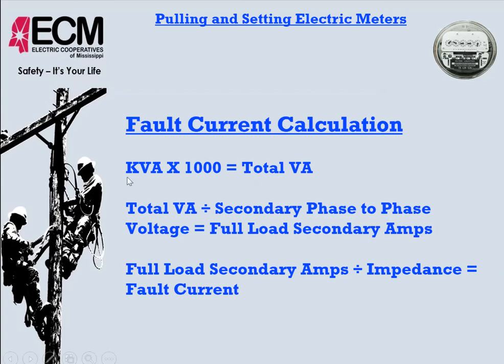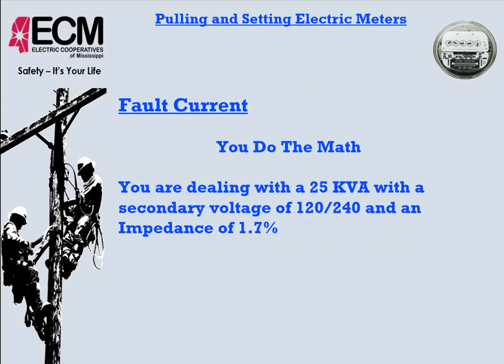So what you would do is take the kVA, multiply it times 1,000, which would give us the total VA, the volt amps, and then take the total volt amps and divide it by the secondary phase-to-phase voltage. So if it was a 120-240 transformer, you would use the 240 voltage, and that would give us the full load secondary amps that transformer can deliver at 100% load capacity. And then we want to divide it by the impedance of the transformer. And I have some math here for us.